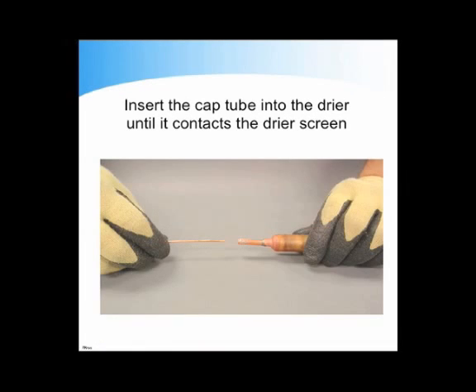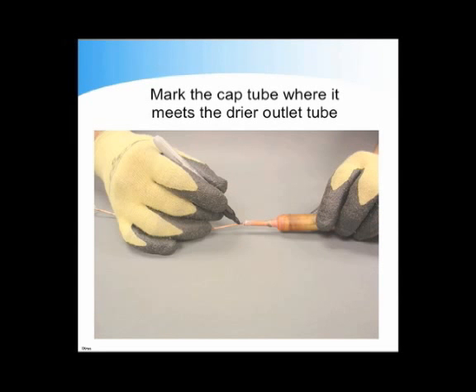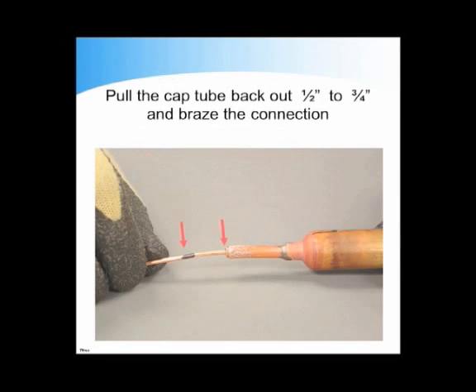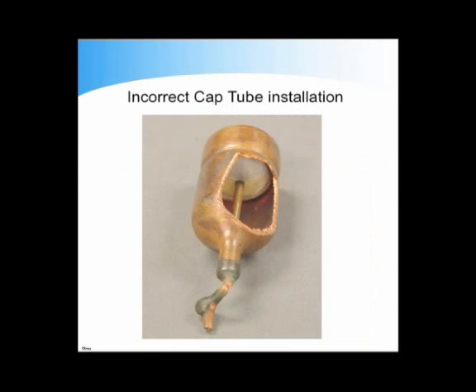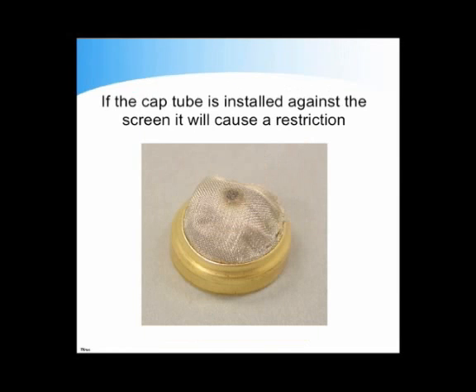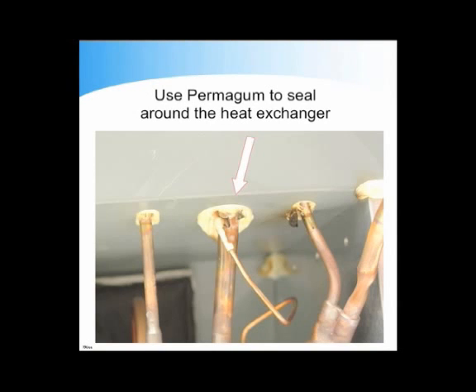Insert the cap tube into the dryer until it contacts the dryer screen. Mark the cap tube where it meets the dryer outlet tube. Pull the cap tube back out a 1/2 inch to 3/4 of an inch and braze the connection. Incorrect cap tube installation: if the cap tube is installed against the screen, it will cause a restriction. Use permagum to seal around the heat exchanger.